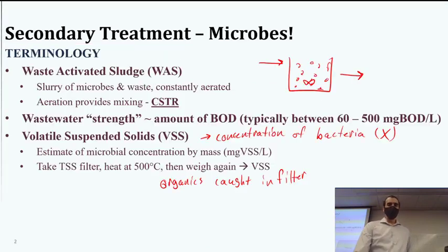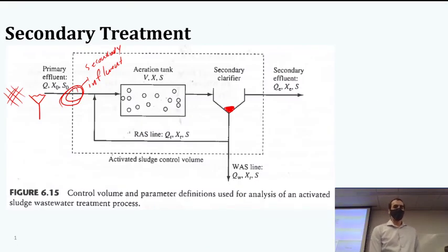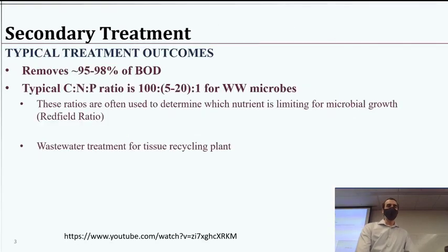In the primary treatment for a wastewater system, we're not doing granular filtration. I probably said the word grain. We do grit chambers and bar racks and screens to catch grains rather than using granular media. There are some cases where we'll use a slow sand filter and let the biological activity happen on the sand itself, so it can be used in wastewater, but generally we don't use granular filtration. That was a difference in process there. That was a good question. Did we have another question?